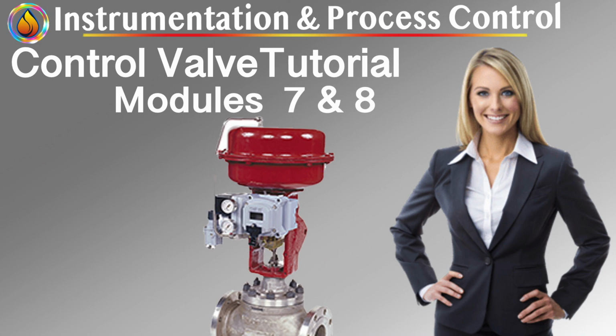Electro-pneumatic positioners. These positioners convert electrical signals into pneumatic control action. Characteristics: electrical input, pneumatic output, improved accuracy over purely pneumatic designs, moderate tuning capability. Strengths: compatible with electronic controllers, better response consistency, widely used in conventional plants. Limitations: still limited in adaptive behavior, calibration drift over time, minimal diagnostics. They represent a transitional technology between mechanical and fully digital systems.